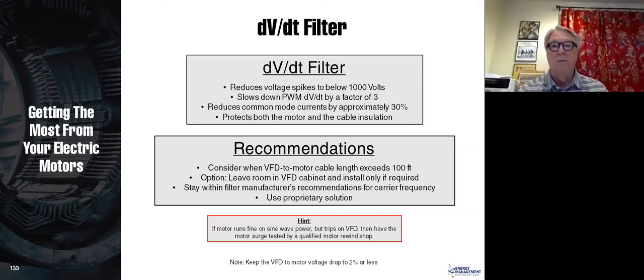A little hint: if your motor runs fine on sine wave power but trips on a VFD, then you should have that motor surge tested with a Baker surge tester by a qualified motor rewind shop, because your motor insulation is on the verge of failure probably, and the VFD is seeing that because it's so sensitive, but your across the line starter doesn't see that. But you certainly want to address that.